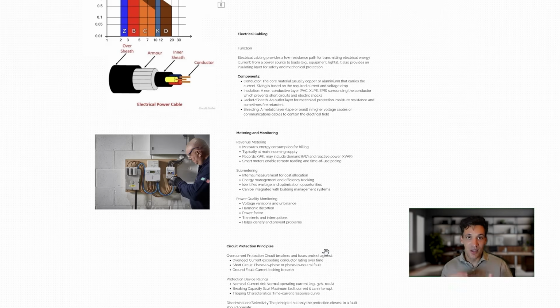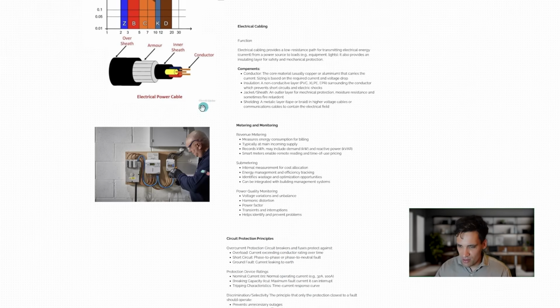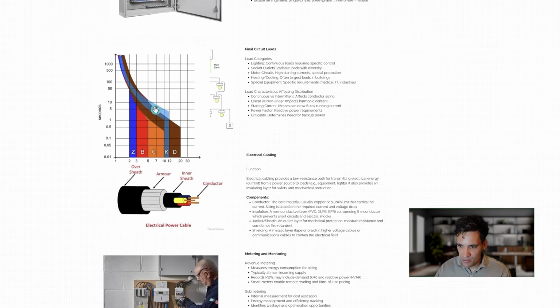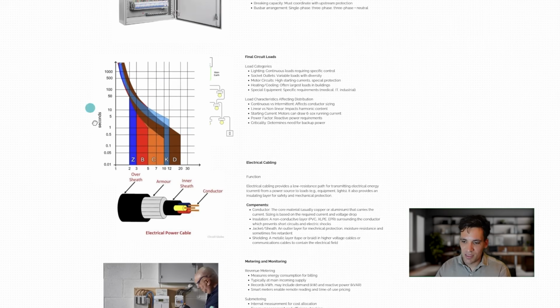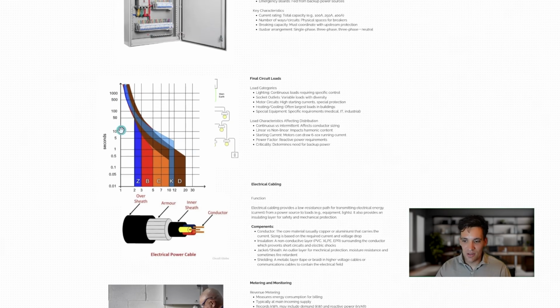It measures the current flowing through a circuit. There's a fault, it trips, disconnects the circuit so it's safe to operate. So circuit protection and earthing are fundamental to safe electrical systems. So I don't know why I've got this diagram up here, but I put it in the wrong spot. But all overcurrent protection has a time current curve.